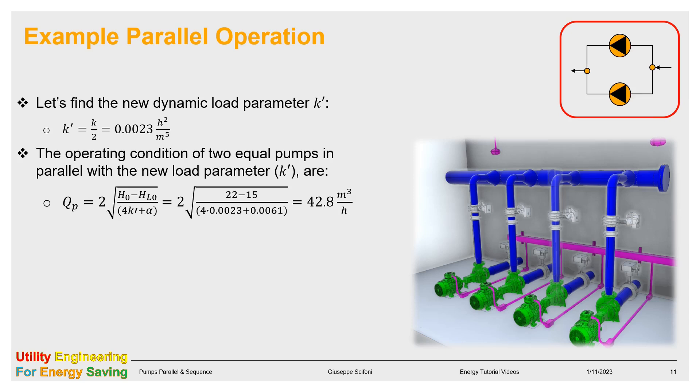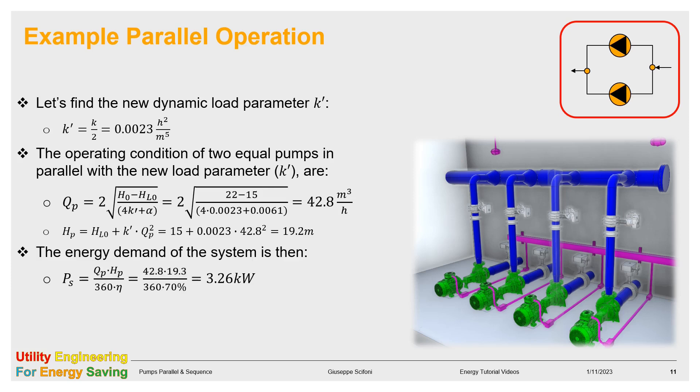The flow of the parallel we can find soon by using the formula seen at slide number 5. We get QP equals 42.8 cubic meter per hour. Similarly, as per the sequence operation, we get the head HP that turns into 19.2 meter. The energy demand is now 3.26 kilowatt.